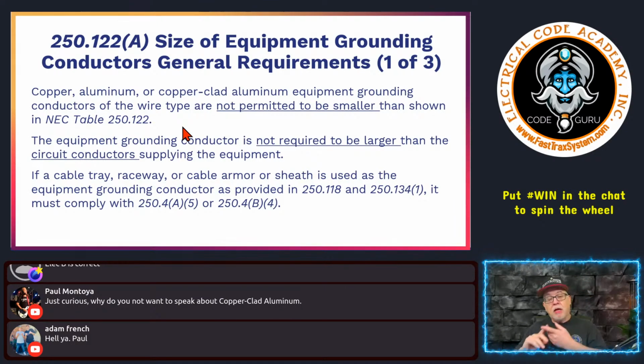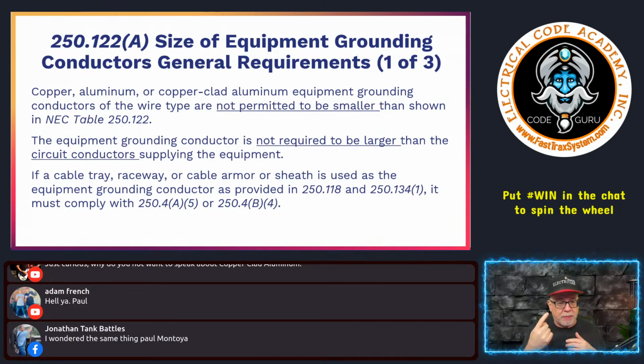Right now, in 250.122, you're going to have an A, a B, a C, a D, an E. You're going to have these rules that you've got to keep in mind, so you don't just get blindsided and say, oh, I'm just going to go, in all cases, to Table 250.122. You might have parallels you have to worry about with circuits, and you need to understand the rules in 250.122(F). You might have multiple circuits in a raceway, and you really only need one properly sized equipment ground, that type of thing. So it's important to know each one of these requirements. But we're just going to talk about sizing right now.